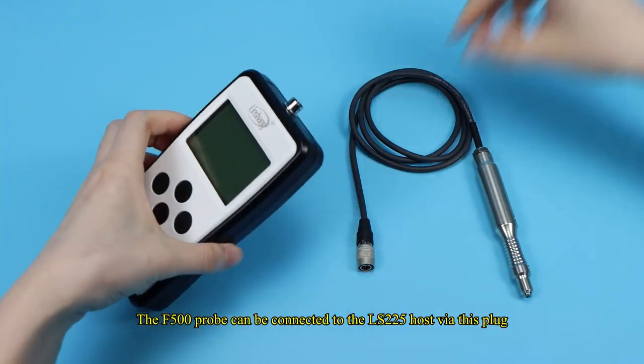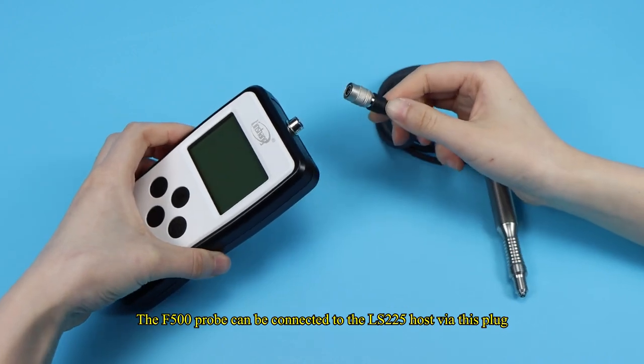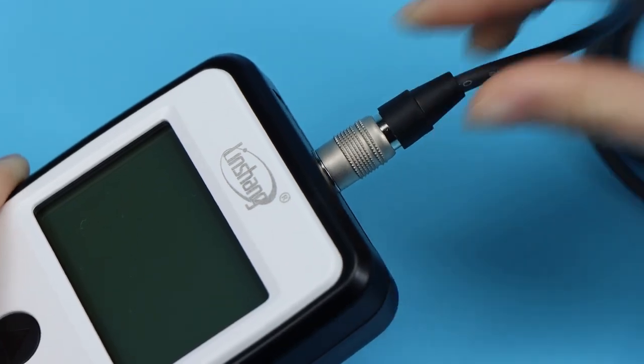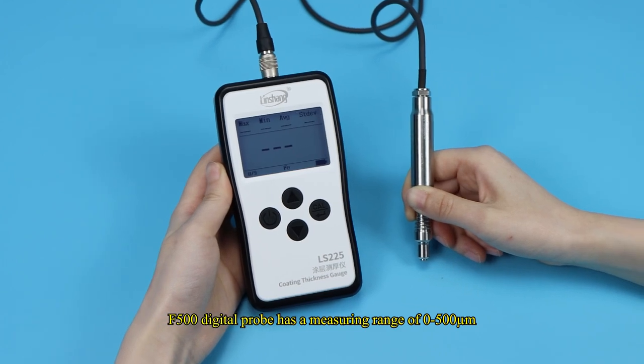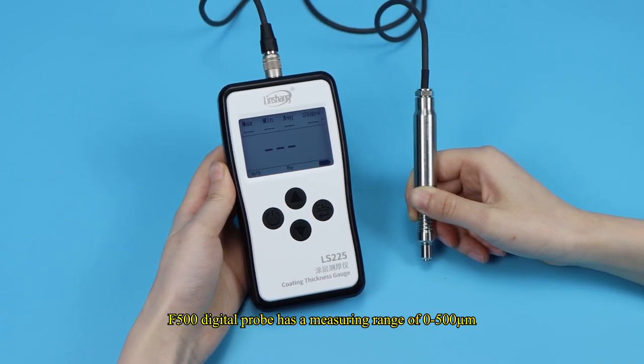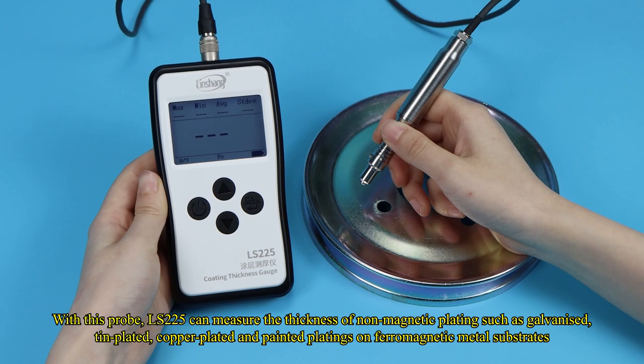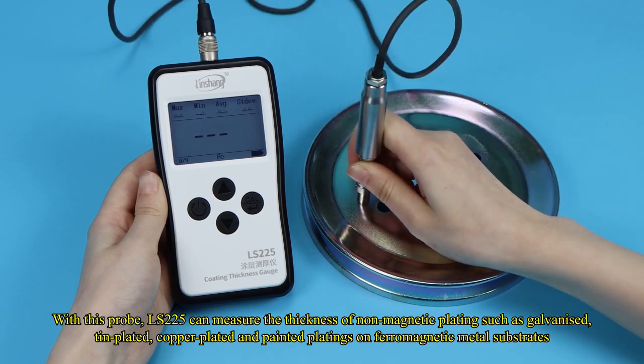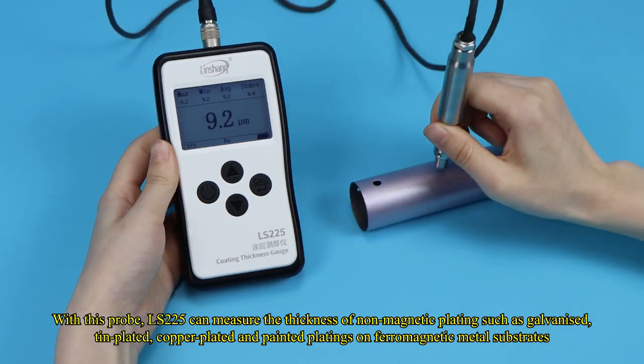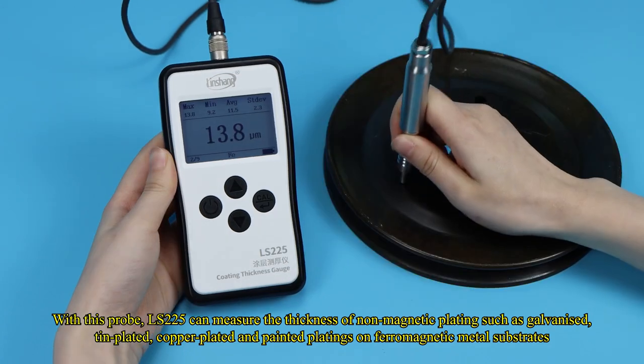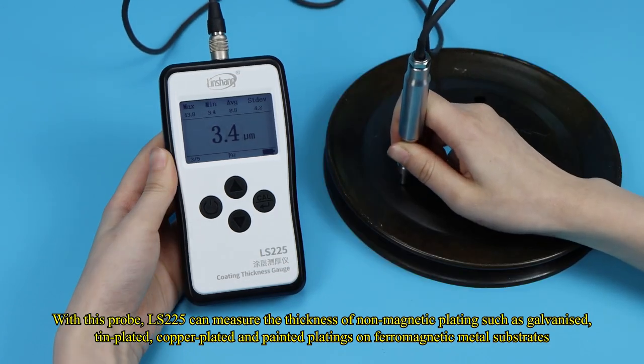The F-500 probe can be connected to the LS-225 host via this plug. F-500 digital probe has a measuring range of 0 to 500 micrometer. With this probe, LS-225 can measure the thickness of non-magnetic platings such as galvanized, tin-plated, copper-plated and painted platings on ferromagnetic metal substrates.